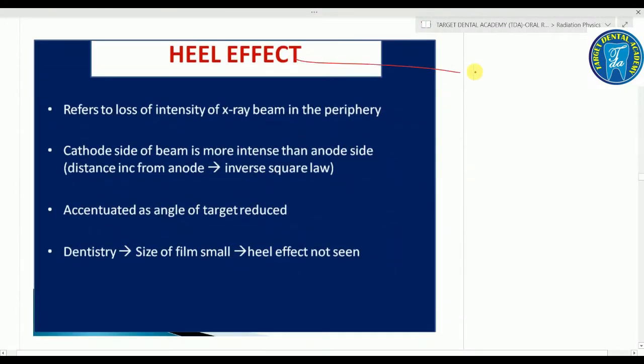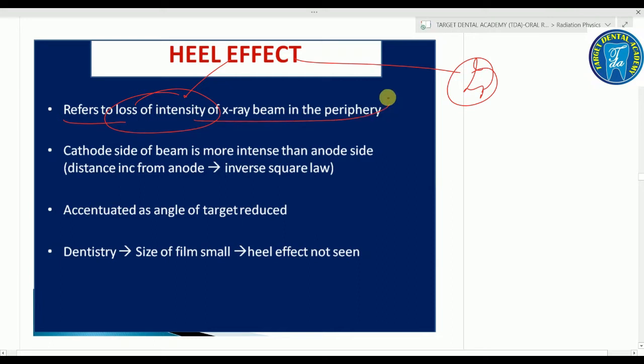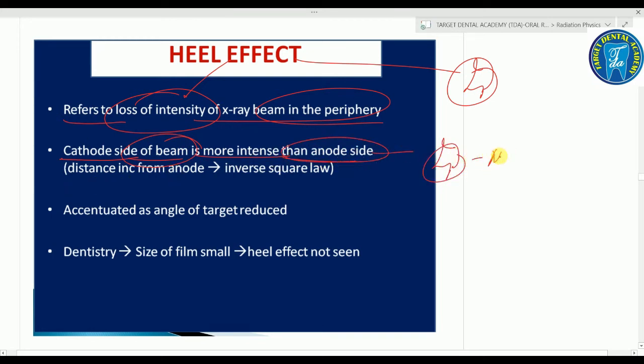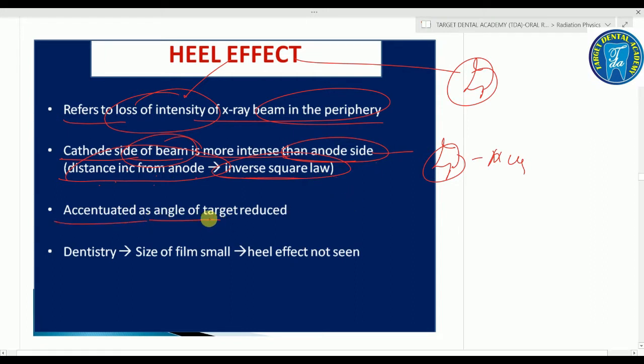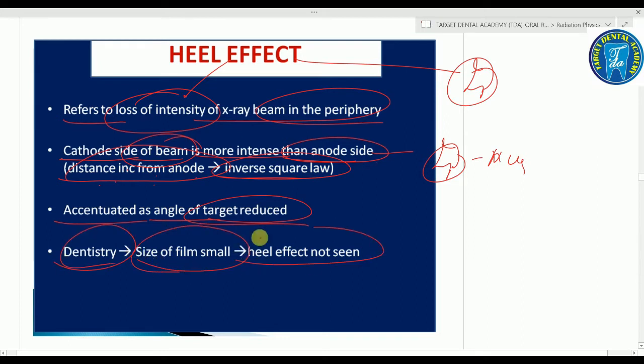The heel effect refers to the loss of intensity of the X-ray beam at the periphery. The cathode side of the beam is more intense than the anode side. Intensity decreases with increasing distance from the anode (inverse square law). In dentistry, if the film size is small, the heel effect is not seen.